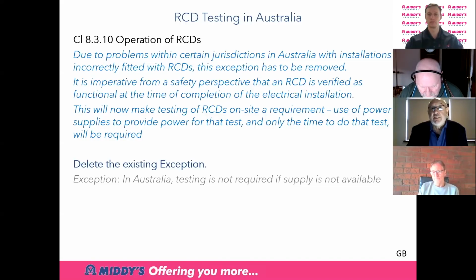RCDs, as we all know, have reduced the amount of electrocution and the amount of shock dramatically over the last 20 or so years. And so we want to make sure that we keep testing these RCDs and make sure that a new installation does perform as it should do with an RCD. So we've deleted that exception as of this amendment.